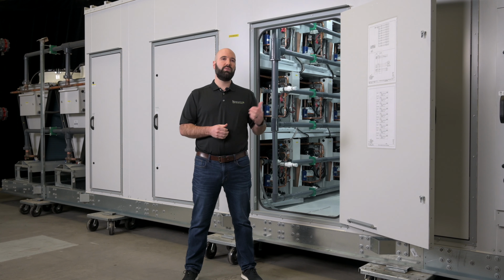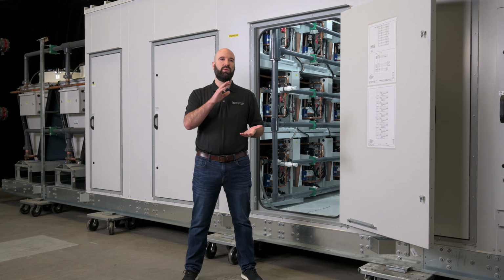You'll notice behind me that we've also got relatively small coils, and again, the purpose behind that is you can get a lot of compressor tonnage in relatively small coils this way and eliminate any moisture carryover and ensure that we've got a positive draining happening between the compound drain pans behind me. We'll take a look at the cutaway because I can talk a little more freely about how that technology all looks together and show a picture of what 120 tons of these pods looks like. It's pretty impressive, but ultimately this 55-ton frame size behind me is about the sweet spot for us and generally for the customer base.